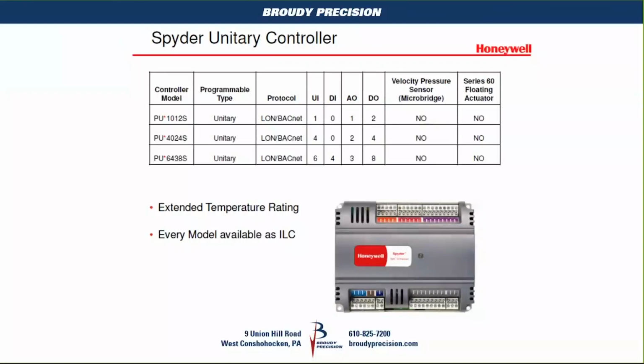Now, the other type of Spyder that is manufactured is the unitary type, and we use this particular model for just about everything else that doesn't require a flow bridge. Now, this is not to say that you can't use a VAV controller. It's fully programmable. You can put anything program-wise into a Spyder that you want to. If you wanted to use the flow bridge for a very low differential pressure application, you could do that. I'm not a big fan of that. Don't recommend that.